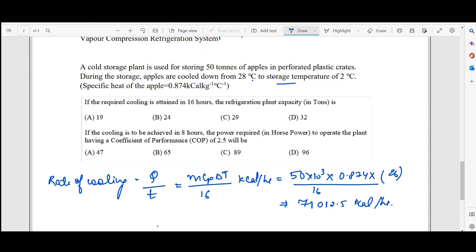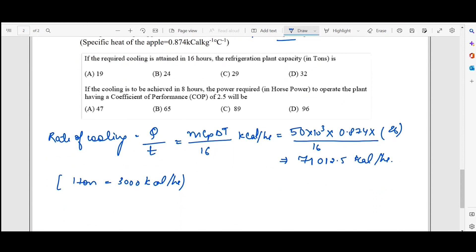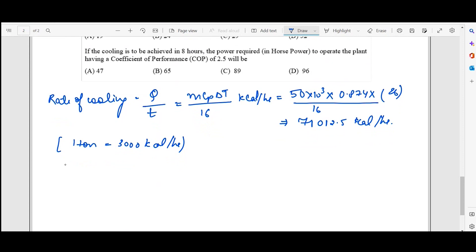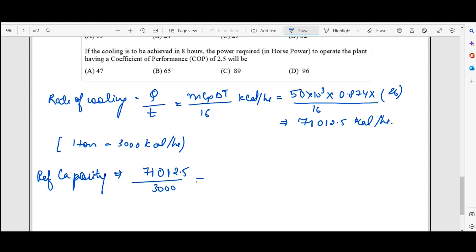The question asks for the refrigeration capacity in tons. Using the conversion factor — one ton equals 3,000 kilocalories per hour — we divide 71,012.5 by 3,000, which gives approximately 24 tons. So 24 tons is the refrigeration capacity of this plant.